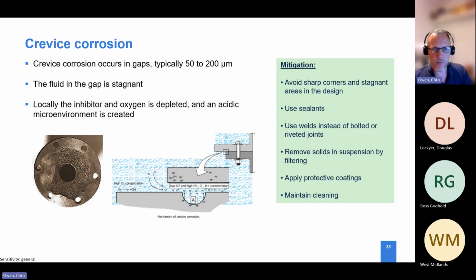Other types of corrosion which initiate, we call crevice corrosion. Crevice corrosion is normally associated with two different components sort of next to each other, either a flange plate or a bracket or something like that. However, crevice corrosion also occurs within pipework systems, particularly if the internal weld bead has not been trimmed properly.